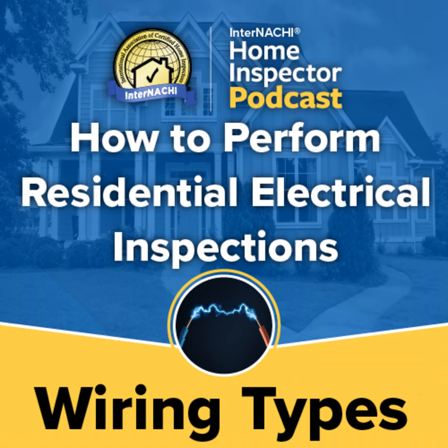Electrical distribution. Wiring types. Wire types for North American wiring practices are defined by the standards issued by Underwriters Laboratories, the Canadian Standards Association, the American Society for Testing and Materials, the National Electrical Manufacturers Association, and the Insulated Cable Engineers Association. Most circuits in the modern North American home and light commercial construction are wired with non-metallic sheathed NM cable, often referred to by the brand name Romex. This type of cable is the least expensive for a given size and is appropriate for dry indoor applications.